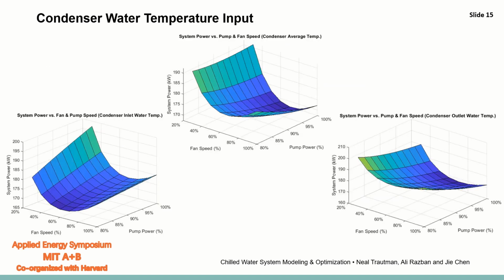And that brings us to the condenser water temperature input to our chiller model. Initially, the input was supposed to be the condenser inlet water temperature. What we found in our modeling efforts is that the relationship would cause the pump power to constantly go towards its lowest value, which would increase the outlet water temperature to a point, while the condenser water inlet temperature could remain relatively stable. The difficulty with that is it underpredicts the effect that the outlet water temperature will have on the chiller's performance. Some authors recommend using the condenser outlet water temperature for variable condenser flow applications. The graph for that can be seen on the right. We ended up deciding to use a combination of the two when we took the average of both the inlet and the outlet water temperature, which makes the relationship iterative with respect to both variables.